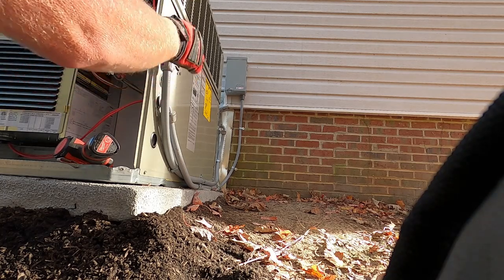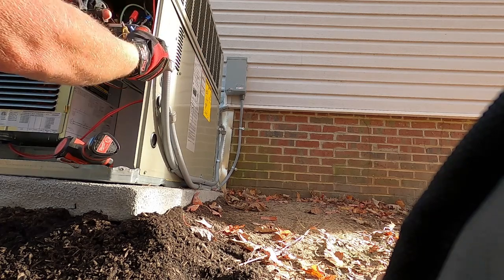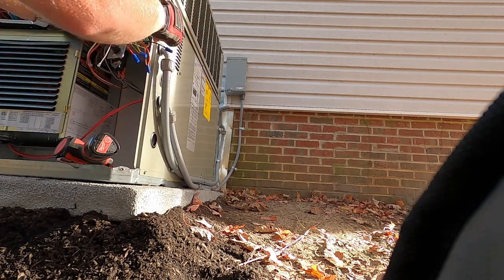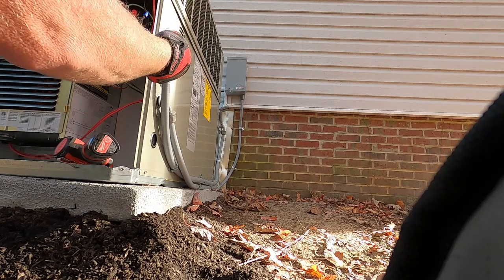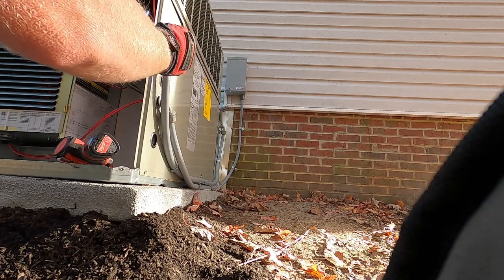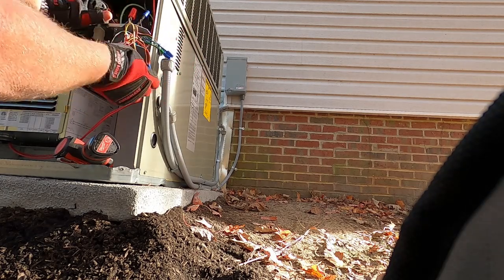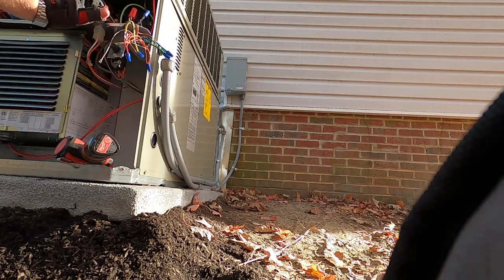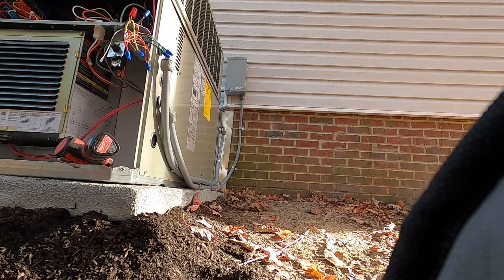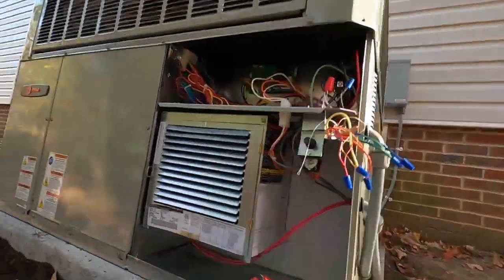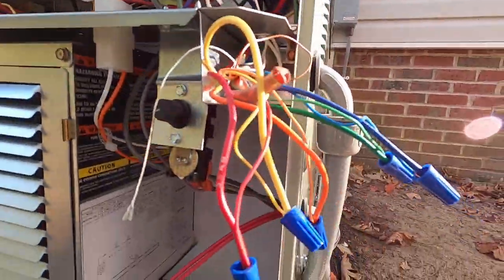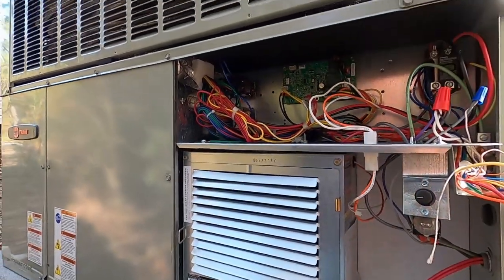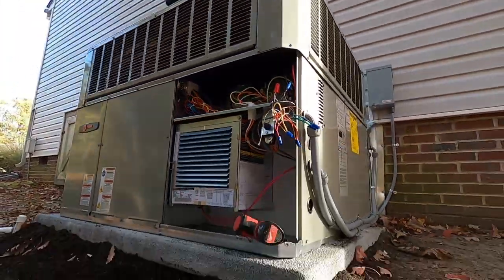So everything in here is snugged up good. So we're going to run in there to the thermostat. I'm going to turn this thing on. We're going to check our refrigerant charge over here and run it in cooling and in heating, make sure everything's operating properly.